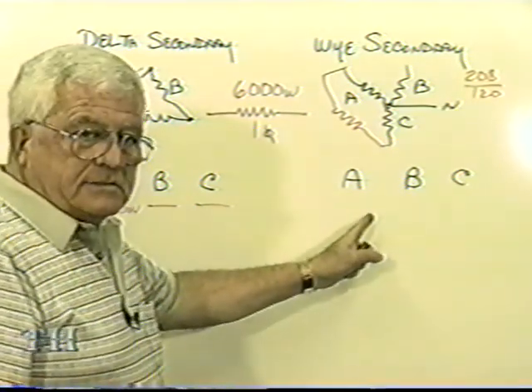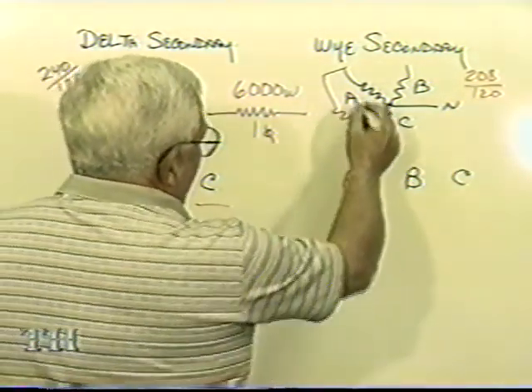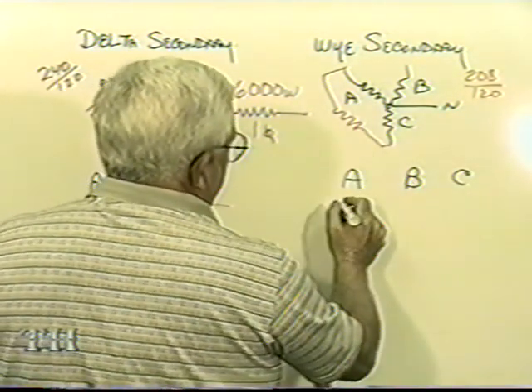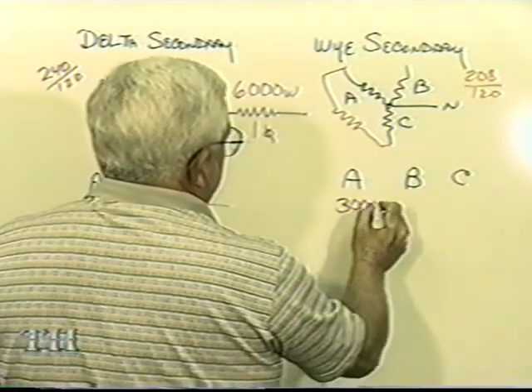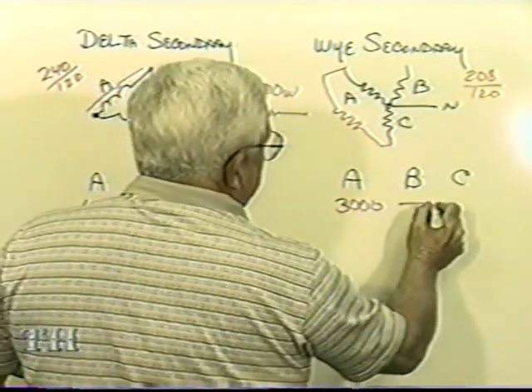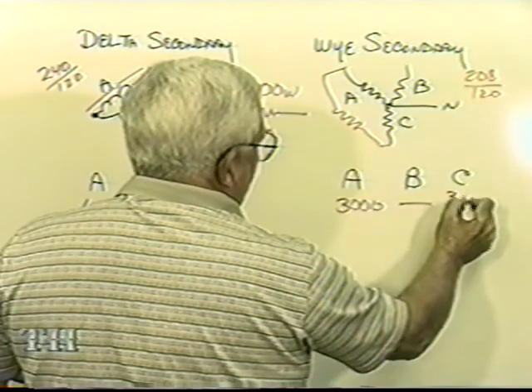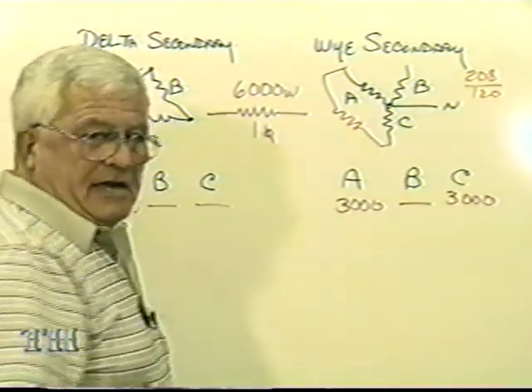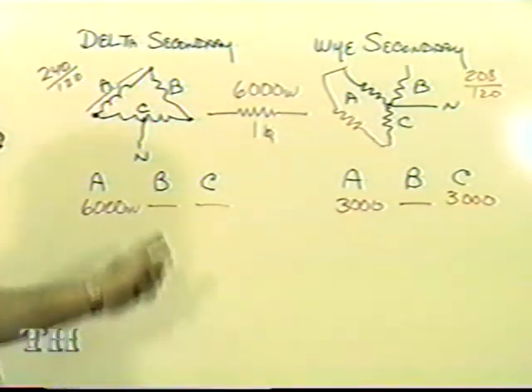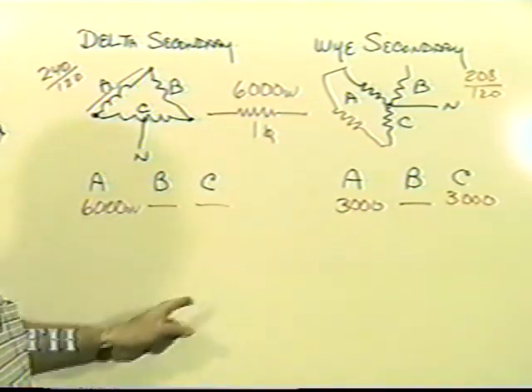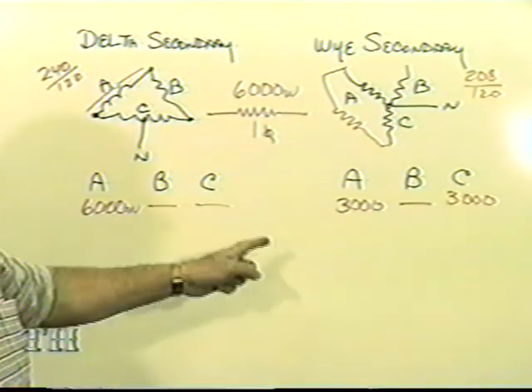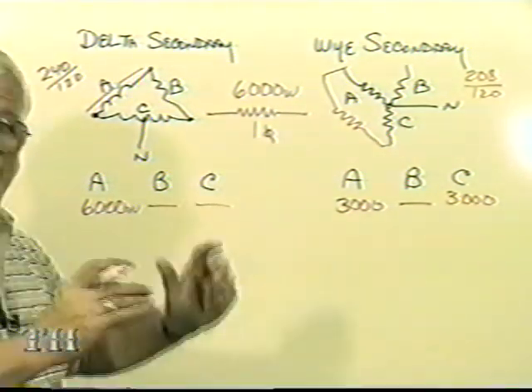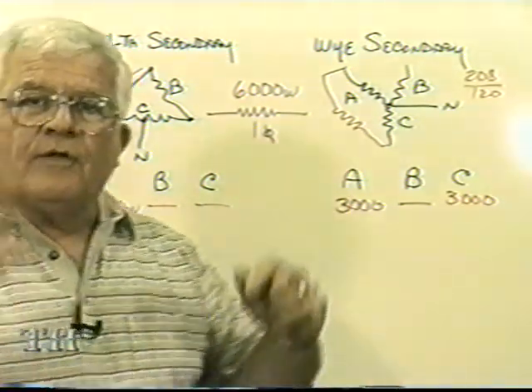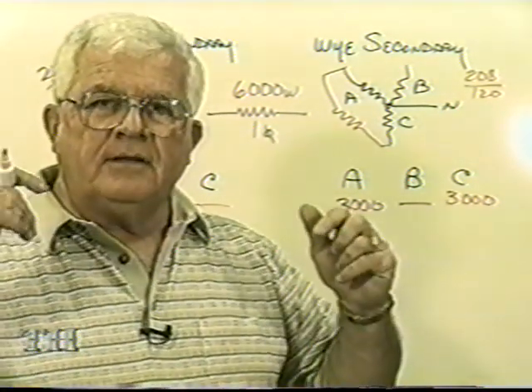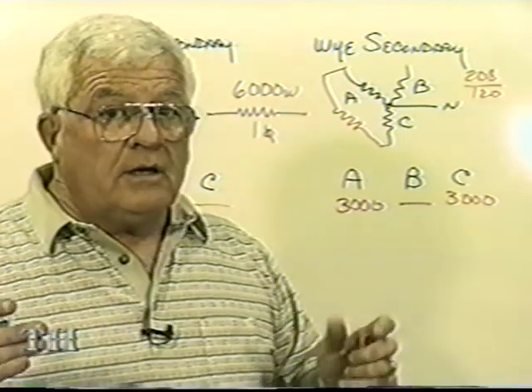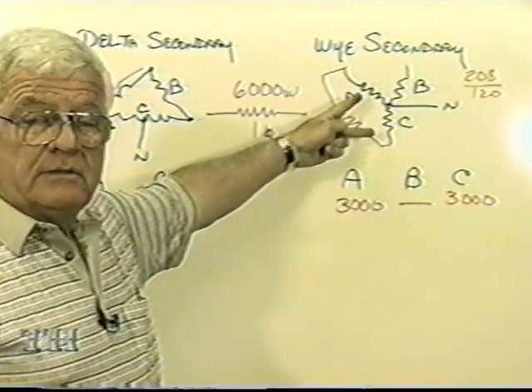Watch how that looks: on A, I would be showing half of that, 3,000. Nothing on B, and C would be picking up the other half. Can you see that with the same load, whether it's connected delta secondary or Y secondary, you have to see where the load goes on the transformer it's connected to?